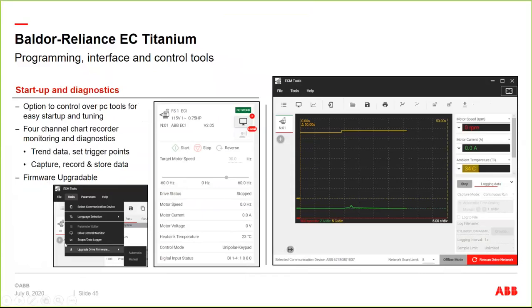And again, these are also all upgradable from a drive firmware standpoint. So again, remember I mentioned we're going to release BACnet. That doesn't mean you're going to have to get a new drive module. You can simply get the new firmware, download it, and upgrade the drive, and it'll be backward compatible. So not a problem.